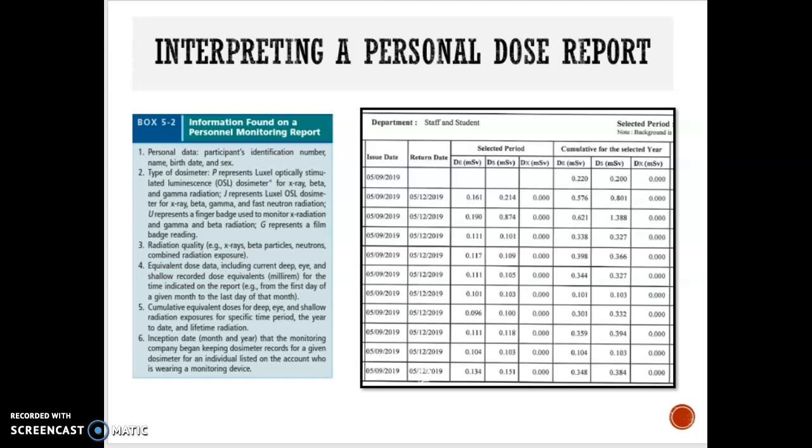Now, based on the work environment, and by that I mean, are you working in radiotherapy, nuclear medicine, the X-ray field, based on the type of work you're doing, dosimeters can be read at different times. It could be read daily, weekly, monthly, quarterly, and that will all depend on the type of radiation work you do. Also, in some institutions, as mentioned before, after pregnancy has been declared, the institution may agree to monitor the worker on a monthly basis. And when the report does come back, they're expecting to see no more than 0.5 millisievert equivalent dose to the surface of the abdomen.